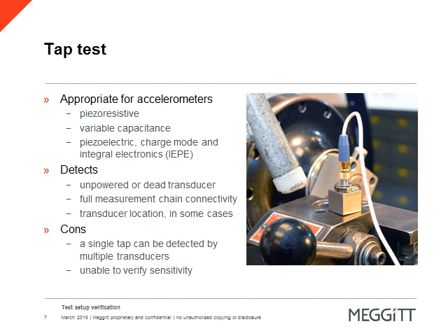Ray, I agree that hitting the accelerometer itself can be destructive, but the tap test method near the accelerometer is one of the most frequent tests performed, and it requires two or more people, which can be labor intensive. It does not validate amplitude or gain settings because of the uncalibrated tap. And if there are multiple accelerometers near the tapping location, multiple measurements will be registered from the same tapping point.